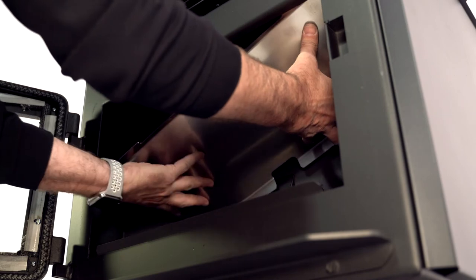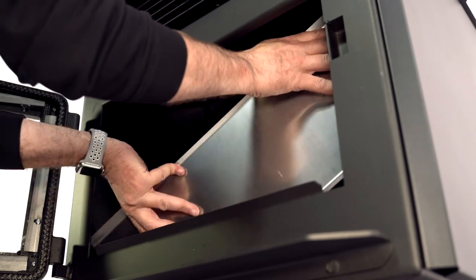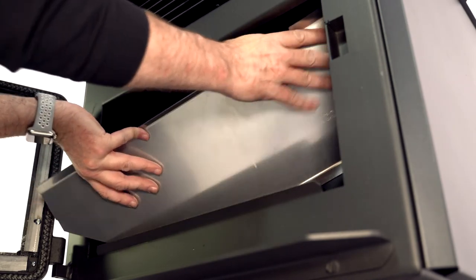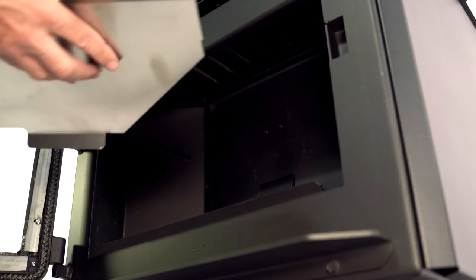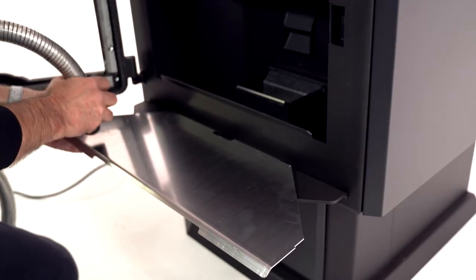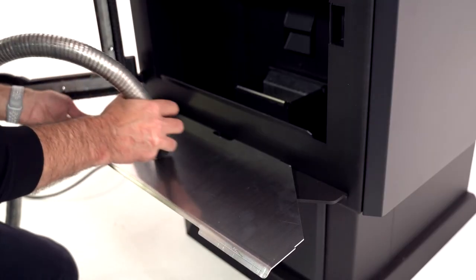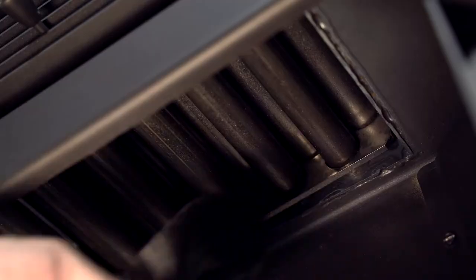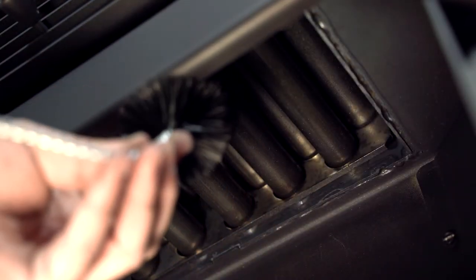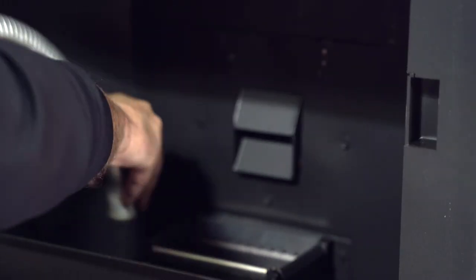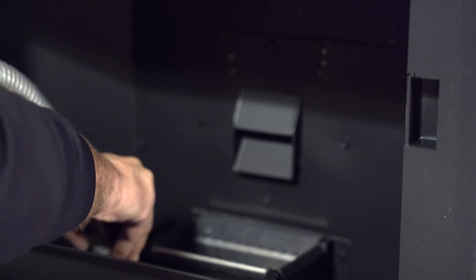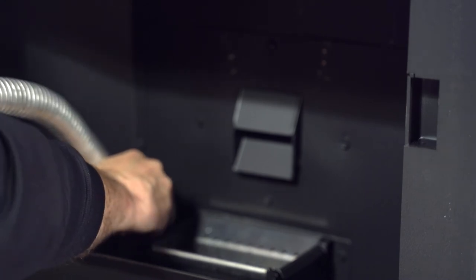Remove the baffle by lifting and tilting it at an angle to slide it out of the firebox. Clean it with the vacuum. Clean the outside of the heat exchanger tubes with a brush, then vacuum the ashes all over the inside of the firebox.